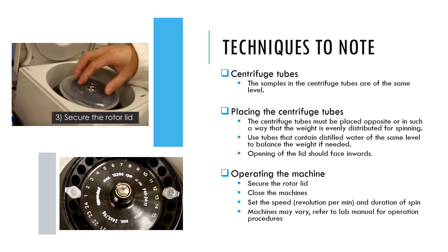When using the centrifuge machine, ensure that the samples in the centrifuge tubes are at the same level. The centrifuge tubes must be placed opposite each other, or in such a way that the weight is evenly distributed for spinning. You may use tubes containing the same volume of distilled water to balance the samples if needed. Secure the rotor lid and close the machine, then set the speed in revolutions per minute and duration. As machines may vary, it is advisable to refer to the laboratory manual for specific operation procedures.